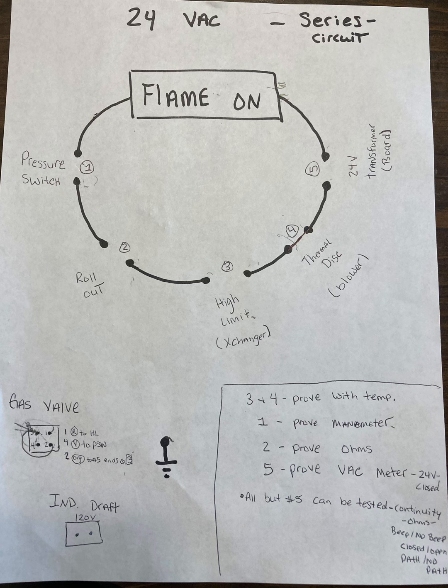Real quick, once again, we talked about safety number 1 was the pressure switch. We need a manometer. They're not very expensive. Get yourself one for $40-$50 and actually figure out what the pressure is. We've got number 2, a rollout switch. This thing can be tested with a lighter. And is it going to trip the switch or is it not?